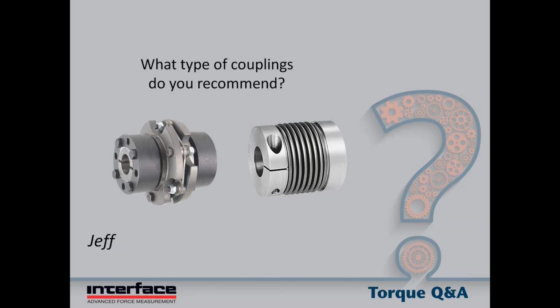Finally, what type of couplings do you recommend? We like disc type couplings. They are positive engagement, zero backlash. They are relatively soft in the directions you want them to be soft, but they're very stiff in the torsion direction. Bellows couplings, which are shown on the right, are also okay, not as recommended as a disc type coupling, but they can be quite soft, which is usually desirable. Things like gear couplings are not recommended. Universal joints, all of those types of couplings tend to have undesirable characteristics for torque measurement.